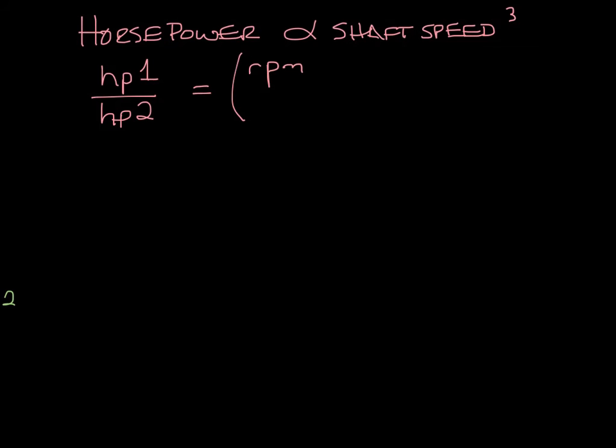So now let's move this over and look at the third law. The third law states that the horsepower varies by the cube of the RPM. So this equation looks like this. Horsepower 1 over horsepower 2 equals RPM1 over RPM2 cubed.